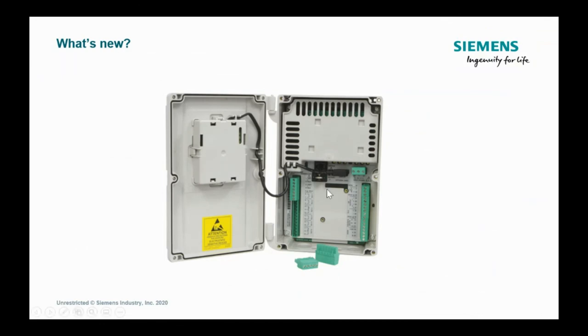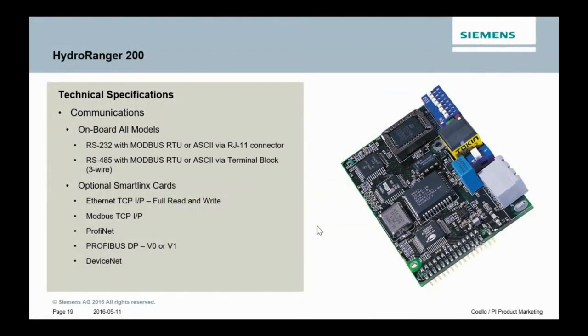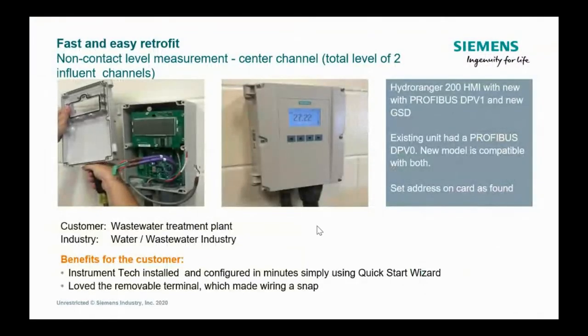The other thing you'll notice on the header, there's a little header here and a couple of standoffs. You can actually pop in communication cards. So if you want to do Ethernet TCP/IP, or Modbus TCP, or Profinet, or some of the advanced communications, you can just snap in a communication card right into that thing, and away you go. The other nice thing is the form factor is still the same. So if you have an old unit and it's all plumbed in, and you want to just upgrade it, but you don't want to take the box off the wall, guess what? 4 screws, you can take the circuit board out, take the door off, slap on the new door, the new circuit board fits in exactly the same place, and voila, you've upgraded in the field.